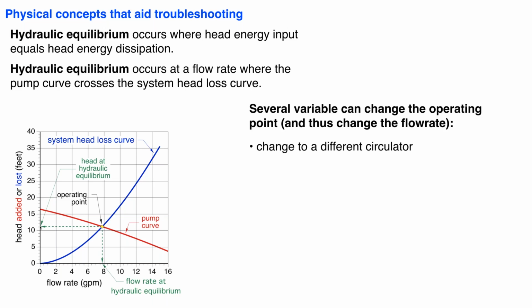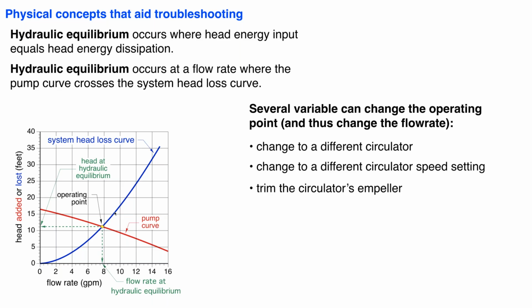One is obviously you change to a different circulator. Go to a bigger circulator, you're going to move this pump curve up, and the operating point is going to slide farther up that blue curve. Or you could change the speed setting on the circulator if it's a multi-speed circulator. Going to a higher speed would be like putting a larger circulator in the system. You don't see this much anymore, but in the old days, trimming the circulator's impeller, actually taking the impeller off, putting it on a lathe and trimming it down to try to tune the circulator to a specific flow rate. Today with variable speed pumps, you don't see much interest in trimming circulator impellers.